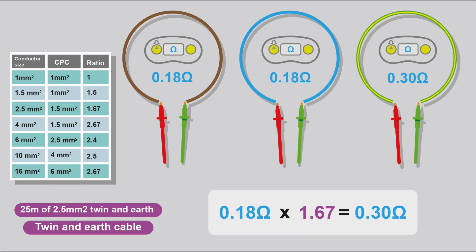So as you can see here, if we had 25m of 2.5 twin-and-earth cable, the line and the neutral would give you a value of 0.18 ohms end-to-end. The CPC would give you a reading of 0.3 of an ohm end-to-end. So say you're doing your continuity of ring final conductors, you're doing end-to-end resistance of your line and your neutral and you're getting 0.18 of an ohm. You can calculate what you should be getting for the CPC.